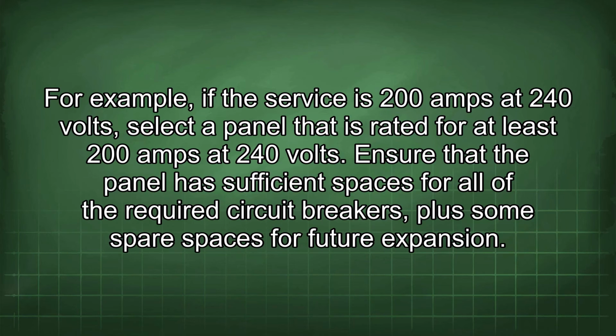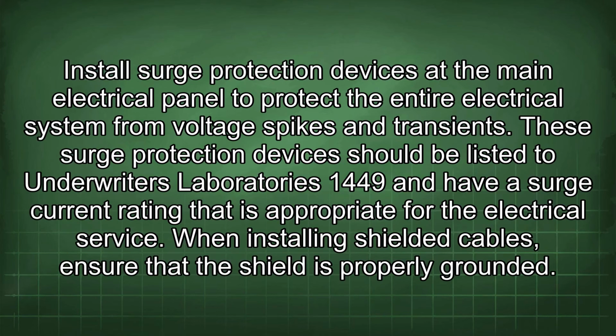Ensure that the panel has sufficient spaces for all of the required circuit breakers, plus some spare spaces for future expansion. Install surge protection devices at the main electrical panel to protect the entire electrical system from voltage spikes and transients. These surge protection devices should be listed to Underwriters Laboratories 1449 and have a surge current rating that is appropriate for the electrical service.